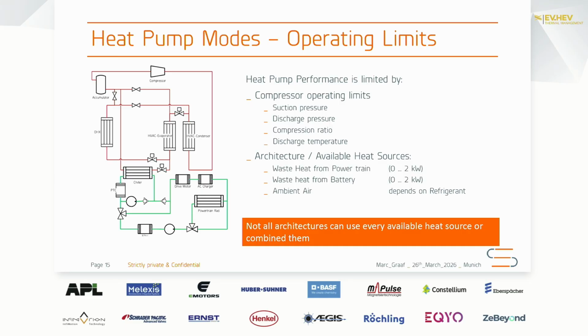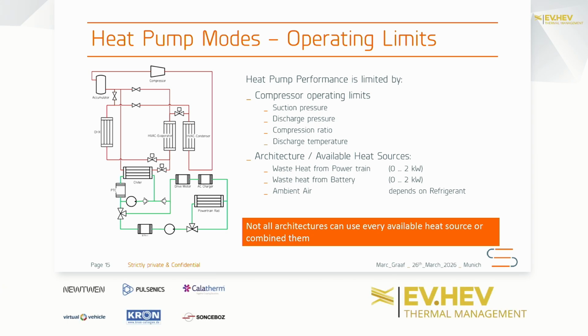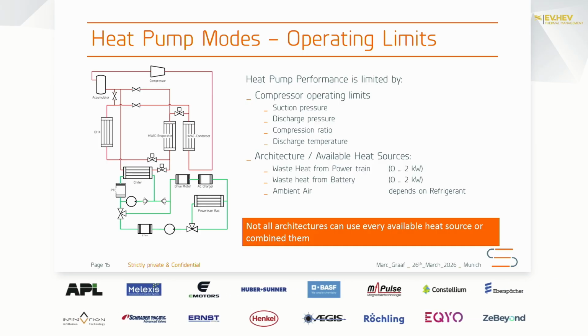The compression ratio: all of these systems are using scroll compressors, which have a limitation on the compression ratio. You can't have ratios of 20, 25. So if you have a YF system and operate it at minus 20 degrees ambient temperature as an air heat pump, you have a suction pressure slightly above 1 bar. But you would need to have 60 or 70 degrees on the air temperature, and you would need 22 bars on the high pressure side for that. A scroll compressor will not be able to realize that, at least not continuously. So those limits are in our simulation models.